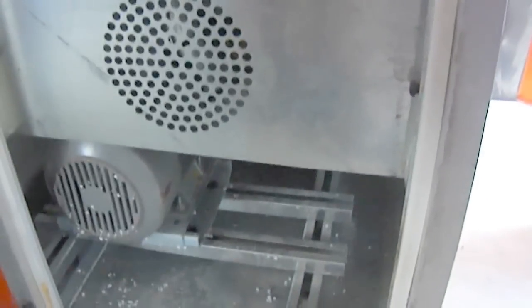So double skin. The advantage of double skin is that, even in the AHU room, the space is not conditioned, so if you go for double skin, the loss is less. For indoor, single skin is also okay as per the cost. But if you want to be on the safe side, double skin is best even for indoor. So they are using double skin. In between the cabinet panels, insulation is there, and that will prevent the loss of cooling effect.